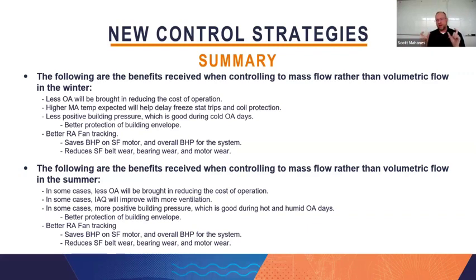And then the return fan tracking becomes an issue when you don't have the right control point of, let's say, 5,000 CFM differential. And that's really a brake horsepower issue for the supply fan being overworked. And it's a lot more wear and tear on the supply fan side versus the return. In the summertime, you get a lot of the same benefits. There's some caveats or changes that can occur. But ultimately, that's kind of where we're at.